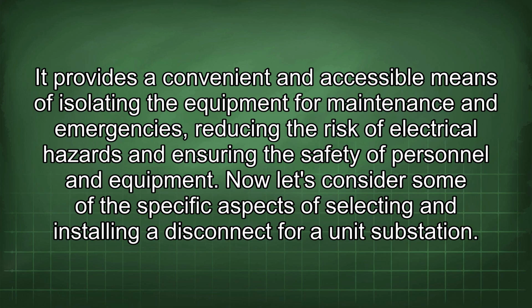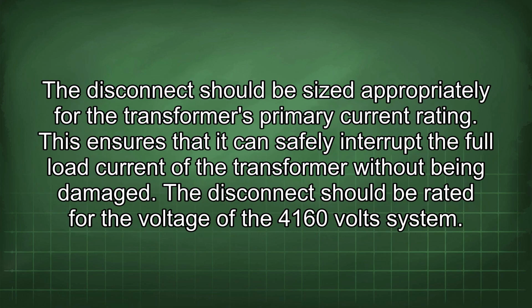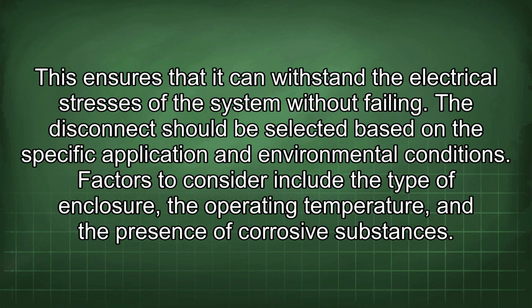Now let's consider some of the specific aspects of selecting and installing a disconnect for a unit substation. The disconnect should be sized appropriately for the transformer's primary current rating. This ensures that it can safely interrupt the full load current of the transformer without being damaged. The disconnect should be rated for the voltage of the 4160-volt system. This ensures that it can withstand the electrical stresses of the system without failing. The disconnect should be selected based on the specific application and environmental conditions.